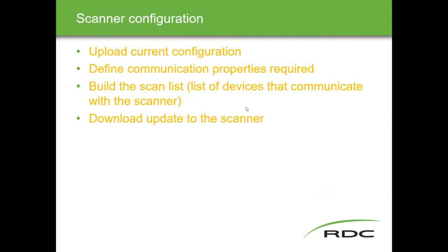Okay, how do we configure one of these scanners? Some basic steps. When you're configuring things, always upload your current configuration first. Always. Anytime you get to the PLC, you're going to do any kind of PLC work whatsoever, upload what you've got now. Save it, back it up, cover yourself. You've got it to fall back on in case you have a really bad day and you just have to say, I'm going back to where I started. So first thing you do, upload current configuration.